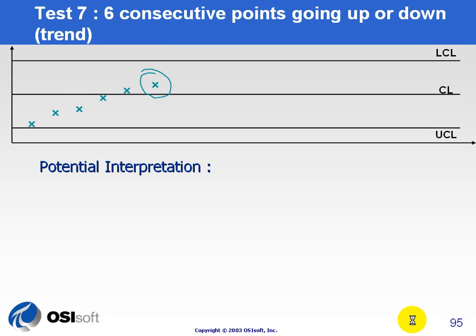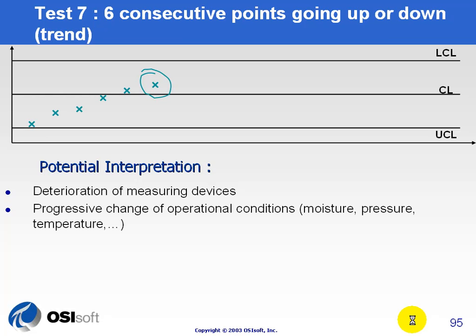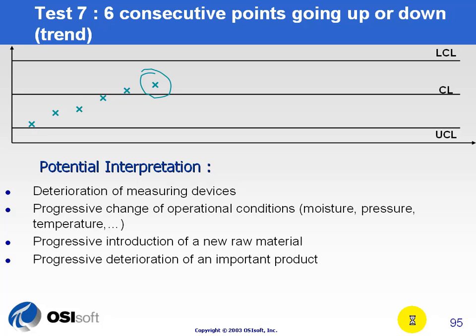Six consecutive points going up or down — also known as trend — the potential interpretation is some kind of equipment that's gradually going out of configuration or gradually deteriorating in performance. If your operating conditions are changing over time, you'll see these kinds of things trend. You're introducing new raw material, you've got product that's deteriorating — catalysts or whatnot — or simply people that are no longer running the process as efficiently as they normally are. You'll find books and books on this. We've been recommending the Western Electric SQC Handbook, which was published in the 50s — now it's the Lucent Handbook, and before that it was the AT&T SQC Handbook. That's really an excellent resource on all these SQC alarm types.